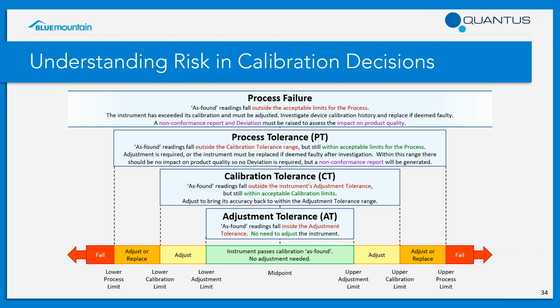However, moving to the next block up in the graphic, where we see calibration tolerance, if the as found readings of the instrument fall outside of that adjustment tolerance but are still within acceptable calibration limits, then those readings fall into the pale yellow blocks that you see on the left and right of the central green block. In this case, it will be necessary to adjust the instrument to bring its accuracy back to within the green range, the adjustment tolerance range. The top and bottom of that calibration tolerance are what we call the lower calibration limit and the upper calibration limit.